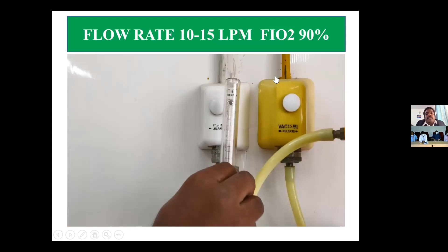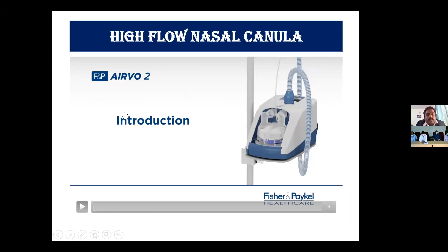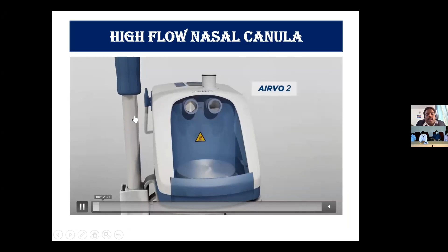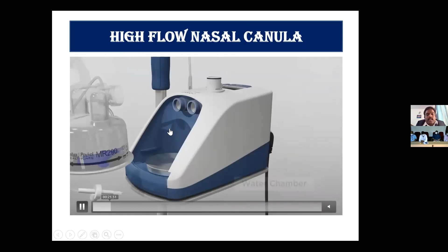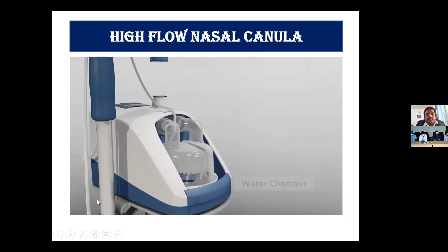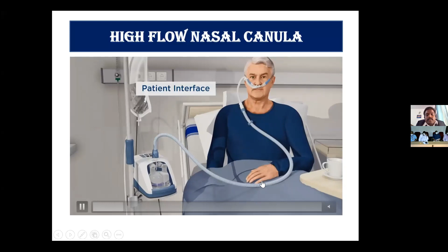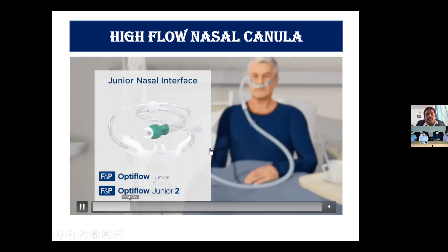And next is the high flow nasal cannula, which is a heated humidifier. So this is the high flow system. We have a chamber here where you can connect the humidification process. The oxygen is connected and the humidifier is connected, and you have a water chamber that is connected to the oxygen pipeline. These pipes have thermal sensor wires that prevent condensation. So you see the oxygen being connected through this, and some amount of environmental air also enters, so mixing of air occurs and later it makes a blend.